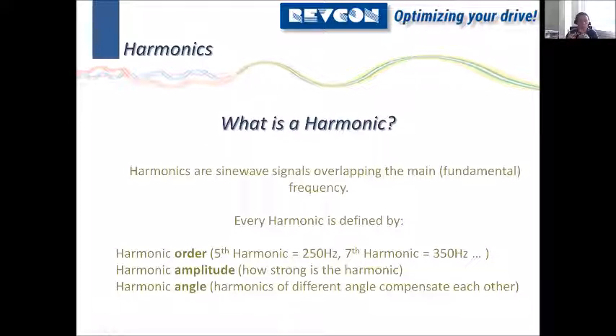Okay, so we have the order, we have the amplitude, and we have an angle. Angle means what kind of angle do we have between the fundamental frequency and the harmonic? What is the phase shift between those two? That's really essential, because harmonics, depending on their angle, may compensate each other. So a fifth harmonic does not necessarily have to add up to a new value. We have to look at their angle. If they have different angles, they would compensate each other partly or completely. And that's, by the way, the main principle of an active harmonic solution, which we will talk a lot about later.